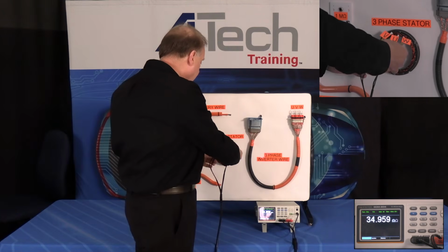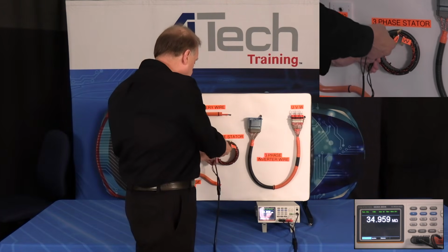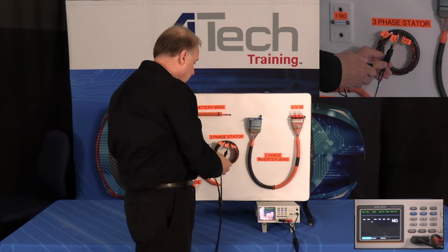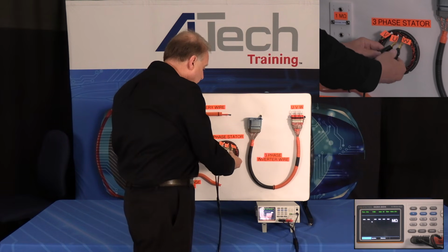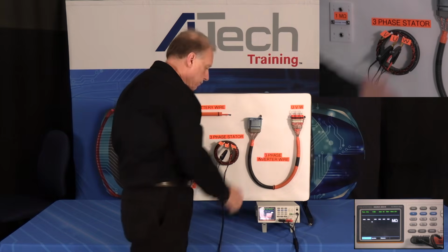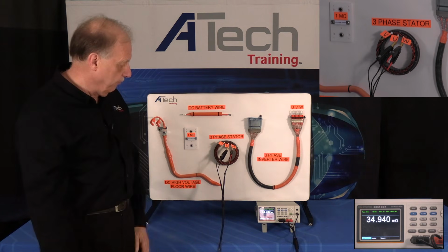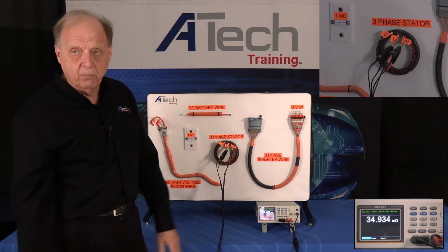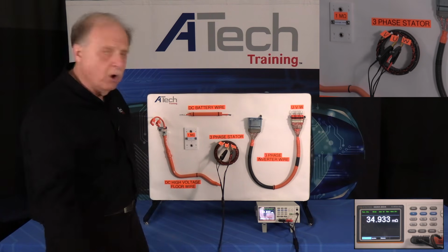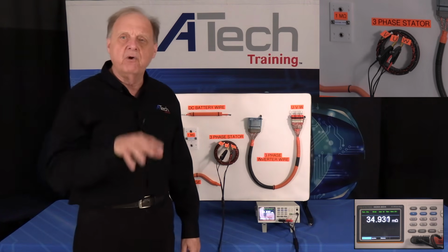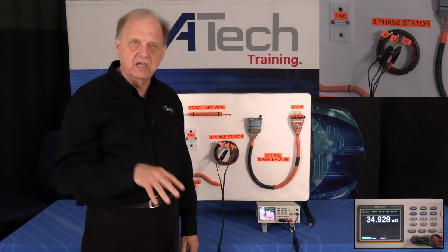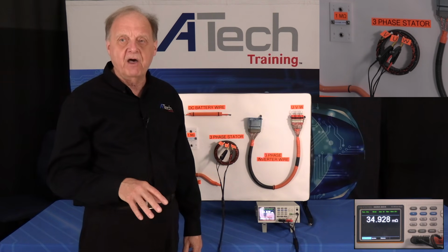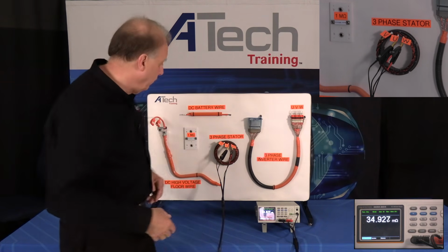The next thing I want to do is come over here and test U to W, making sure I've got a good clip on there. It takes a while for the reading to settle. Notice again we're really close to what we had before. You're looking for a very similar reading on each section. If one reads out significantly different, then you know you have a problem.